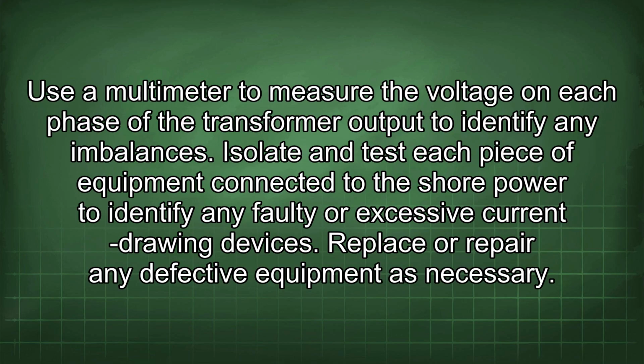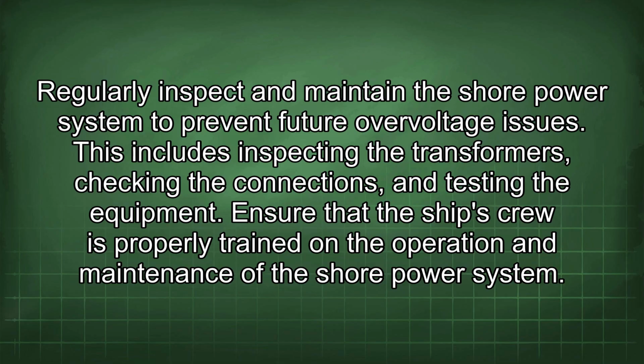Verify that the transformers are rated for the required voltage and load. Use a multimeter to measure the voltage on each phase of the transformer output to identify any imbalances. Isolate and test each piece of equipment connected to the shore power to identify any faulty or excessive current drawing devices. Replace or repair any defective equipment as necessary. Regularly inspect and maintain the shore power system to prevent future overvoltage issues. This includes inspecting the transformers, checking the connections, and testing the equipment. Ensure that the ship's crew is properly trained on the operation and maintenance of the shore power system.